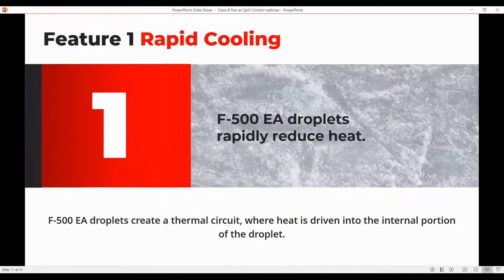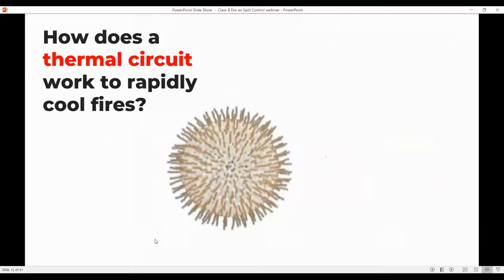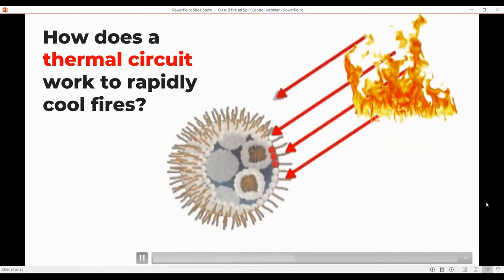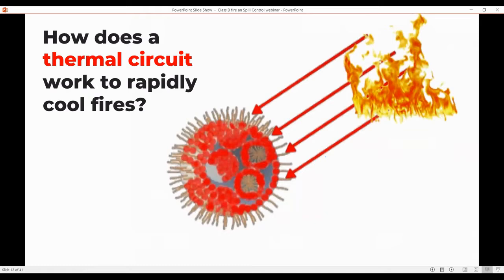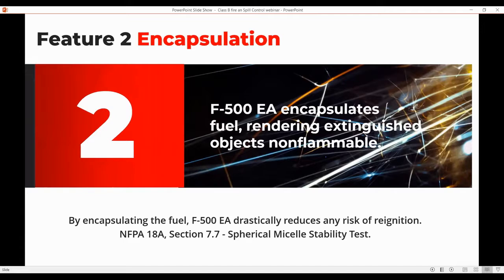The different unique features of F500: the first is rapid cooling. That F500 molecule on the surface of the water droplet acts like a heat sink — it actually absorbs the heat and transfers that heat to the micelles within the water droplet. So as opposed to just using the surface of the water droplet for cooling, you're using the entire mass of that water droplet for cooling. The next thing is the encapsulation of fuels, tested through the NFPA 18A Section 7-7 spherical micelle stability test, showing we can actually encapsulate fuels and render them non-flammable. The guide ratio for achieving total encapsulation is 1-to-8-to-40: one part F500, to 8 parts fuel, to 40 parts water, plus the kinetic energy of the water leaving the hose stream — that will encapsulate the fuel and render it non-flammable and non-explosive.